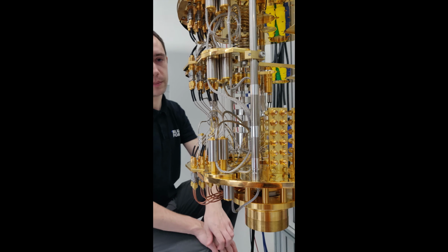One is what we call helium-3 rich, and another is the helium-3 depleted phase. The helium-3 rich phase is non-superfluid, and that's the thing that we are actually feeding from the top, from this condensing line, the thin line that enters the cryostat here. So it enters behind the pulse tube. Here it enters, it goes through this copper thing, which is the small trap. It's just very small, so it's an emergency trap, I would say. Where's the trap? This cylinder here, this copper cylinder.